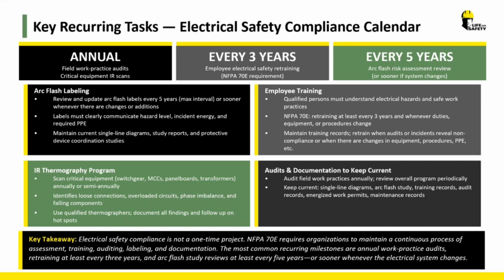Every 5 years you should be reviewing all of your systems—infrastructure, assembly equipment, maintenance aspects, all of it. For a battery or energy storage system, you should be looking at your process and how you arrived at those values every 5 years. The reason is you get different customers with different needs, and your product might change. When the product changes, the arc flash value changes—that's why you need periodic reevaluation to make sure the placard or calorie value associated with it is up to date.